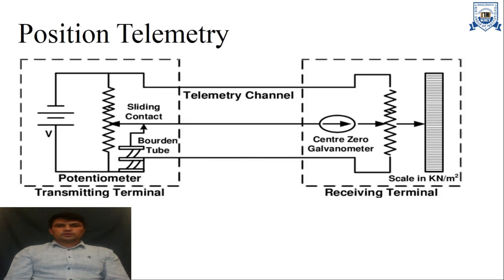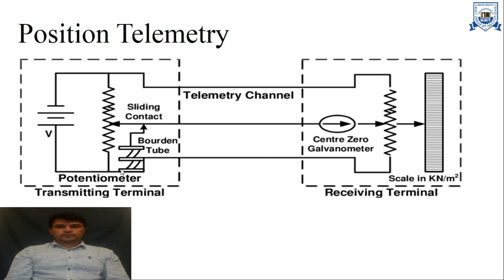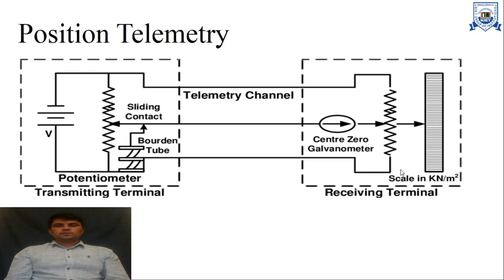Here is the block diagram of position telemetry. We have a potentiometer at the transmitting terminal and again a potentiometer at the receiving terminal. In this case we measure pressure because we use a Bourdon tube. As the pressure increases or decreases, the Bourdon tube shape changes, and as its shape changes, the slider or wiper connected to it also moves, changing the signal at the receiving end as well.